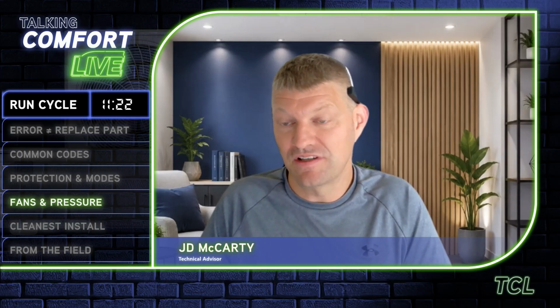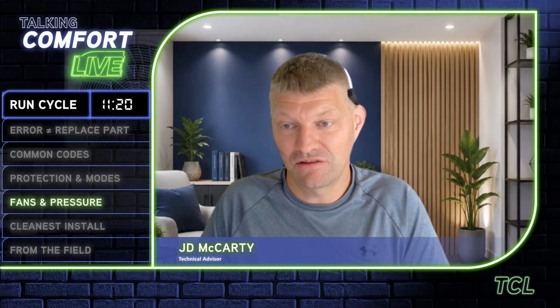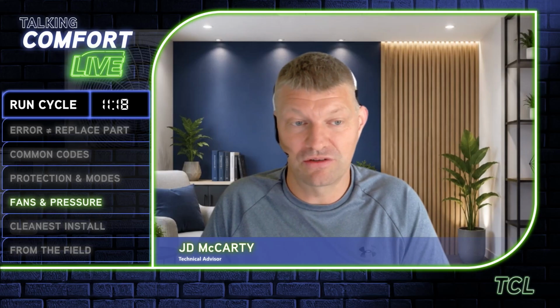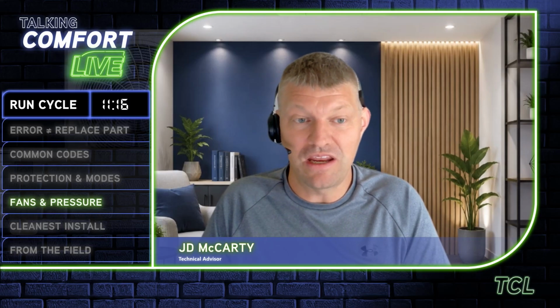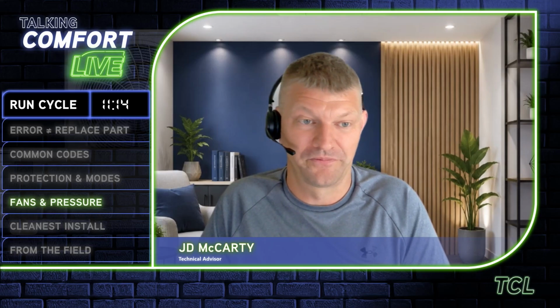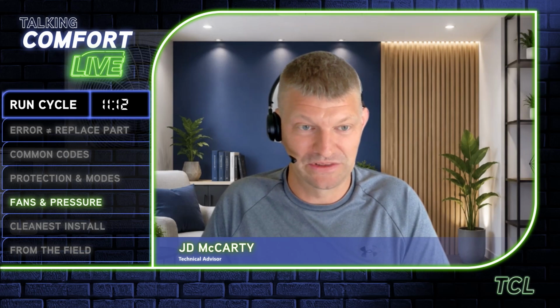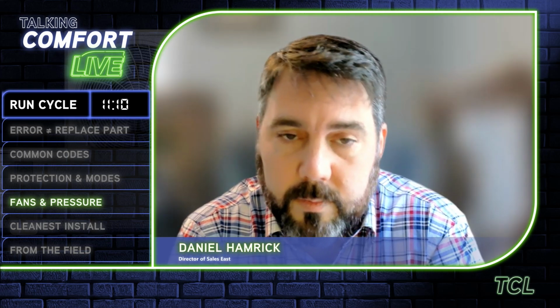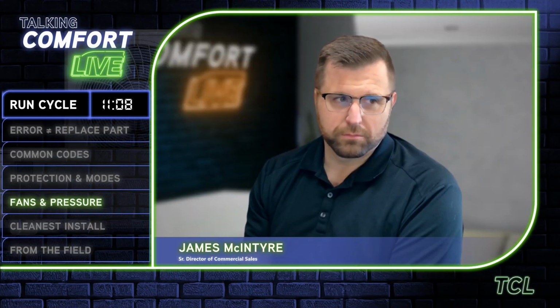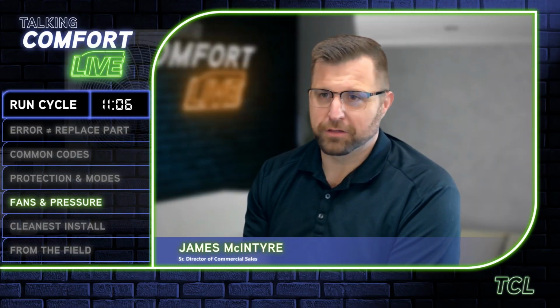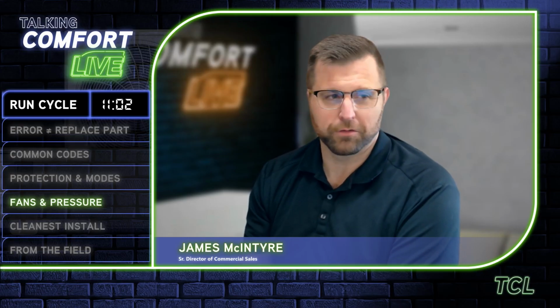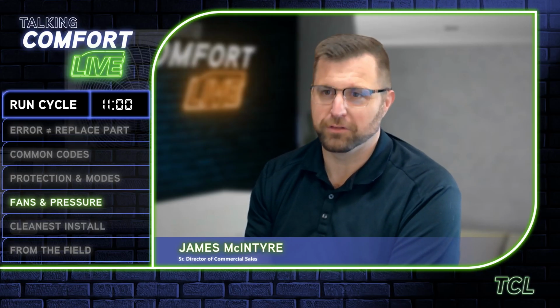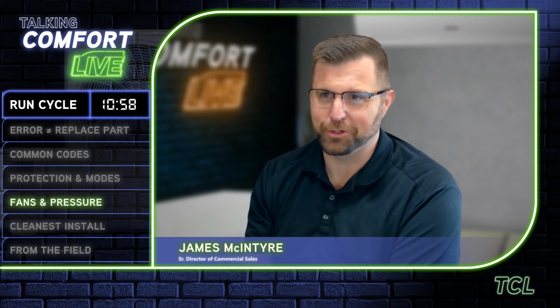I mean, but it could potentially be one of your sensors that control the EEV, out of range, or not allowing that EEV to open. True. Right. Especially on a multi. Now when we talk about things like in those cases where JD was saying, we'll call that one in third place, but it's a distant third place as far as what it could be.